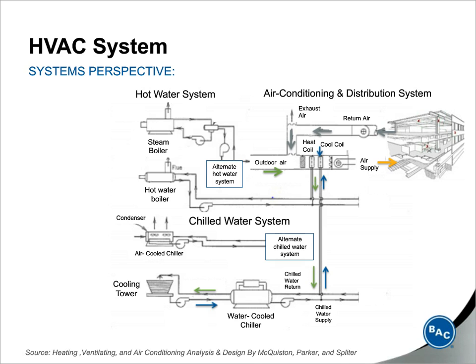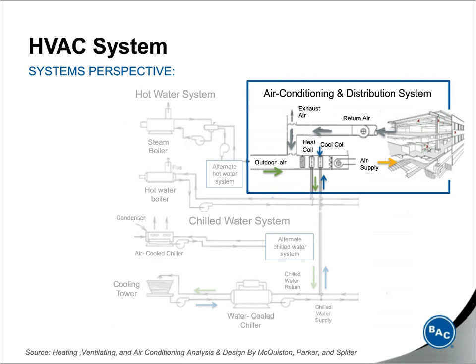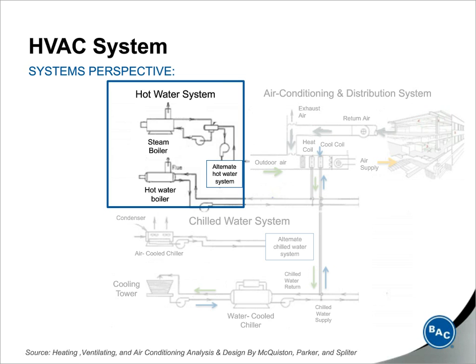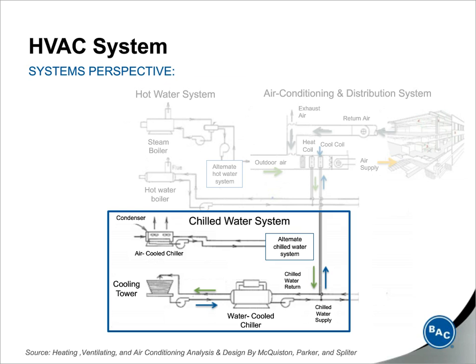Okay, so first you have the air conditioning and distribution system, which includes the air handlers. It conditions the outside air, or the recirculated air, and distributes it to the space that's being cooled or heated in the building. Next, we have a hot water system, and that heats the air that's supplied to the space. And then we have the chilled water system, which as I mentioned earlier, collects heat from the building and rejects it into the outside atmosphere, into the outside air.